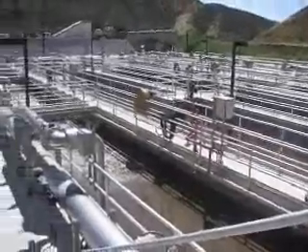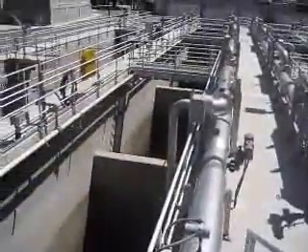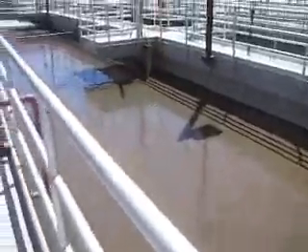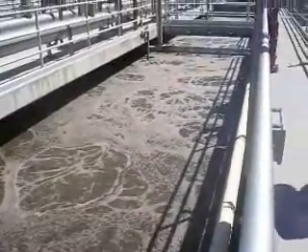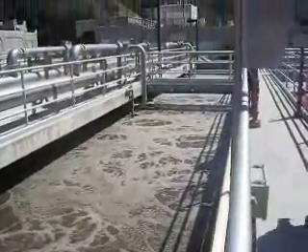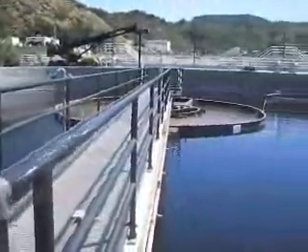Secondary treatment is the next step in which mixed microorganisms consume organic matter in the water. This biological treatment happens in aeration basins. The organisms convert ammonia in the water to nitrite and then to nitrate in a process called nitrification. When air is tapered off, they begin to convert nitrate into nitrogen gas. This is called denitrification.